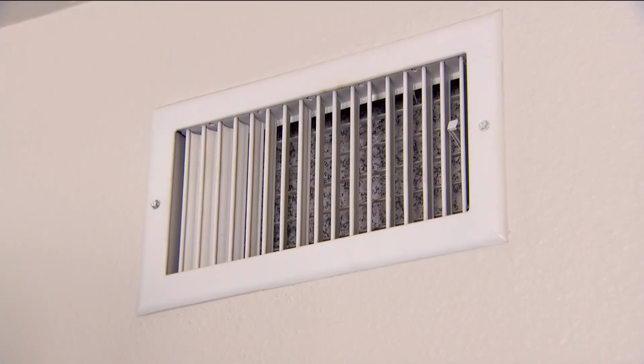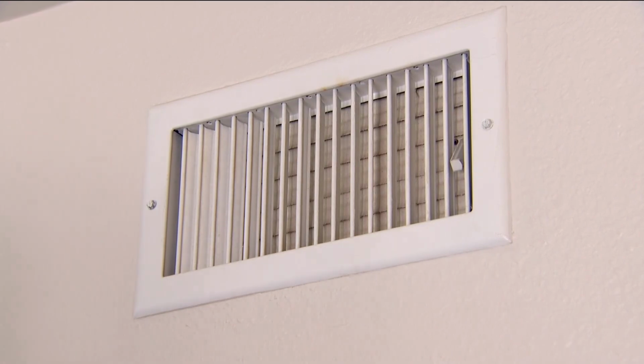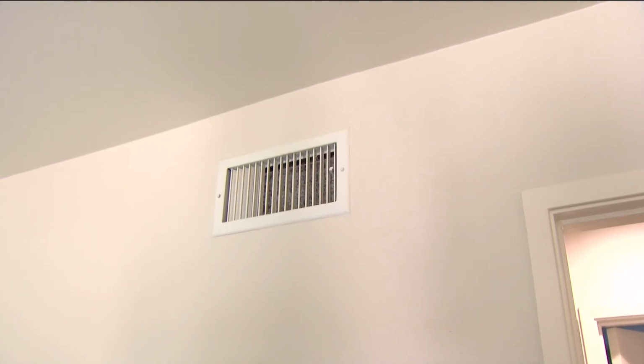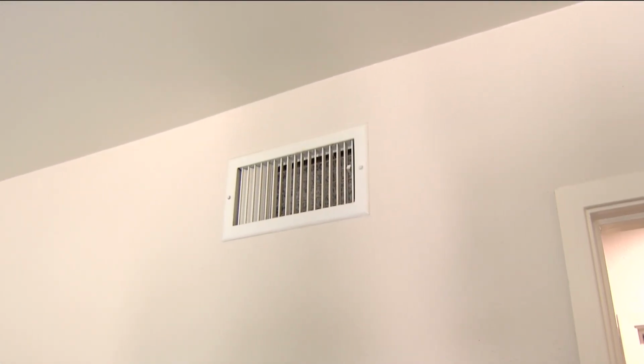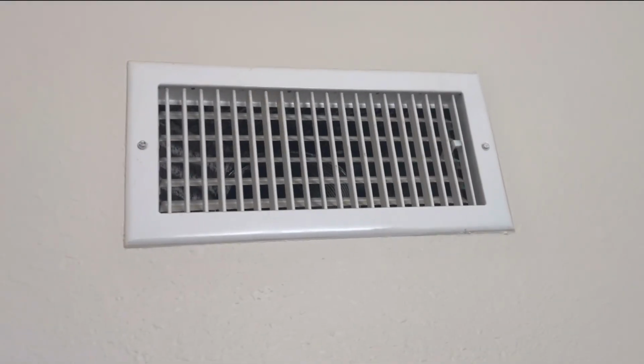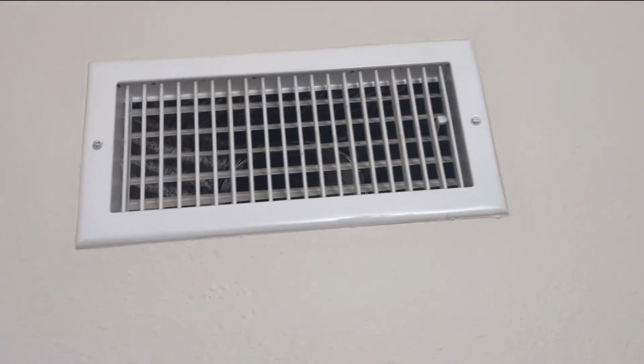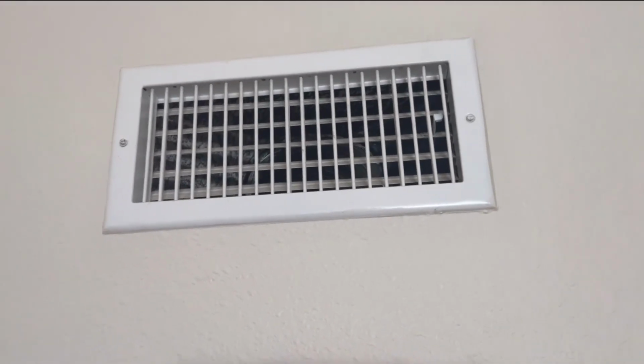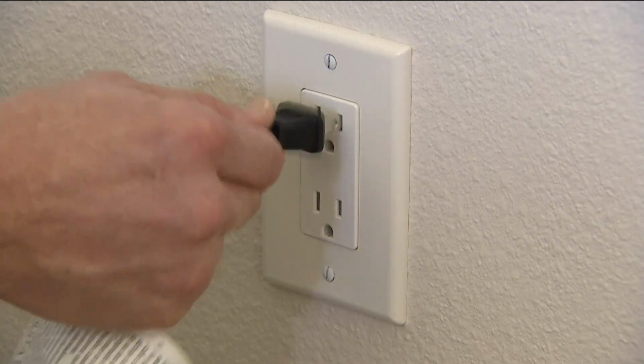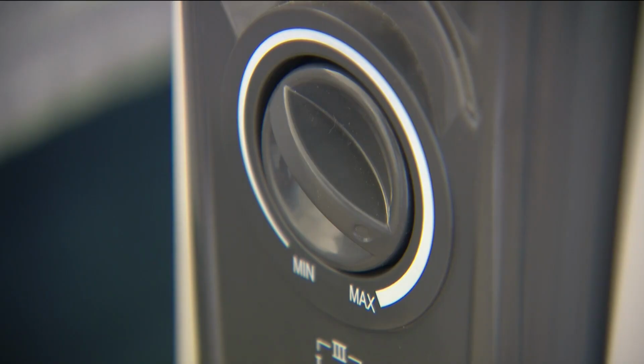What about closing off vents to rooms we don't need to heat? Can that save money? Keith says no, it might actually cause damage. Please understand, your system is designed to have all the vents open. If you start shutting off different registers, you're restricting airflow again, and you can cause havoc with overheating your heat exchanger.